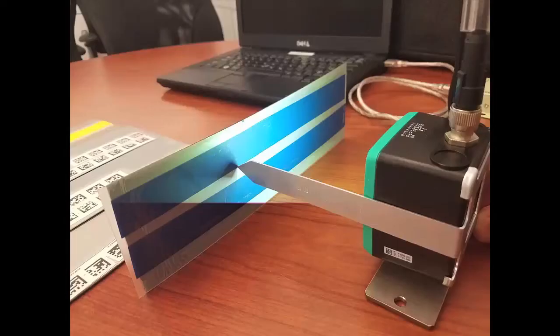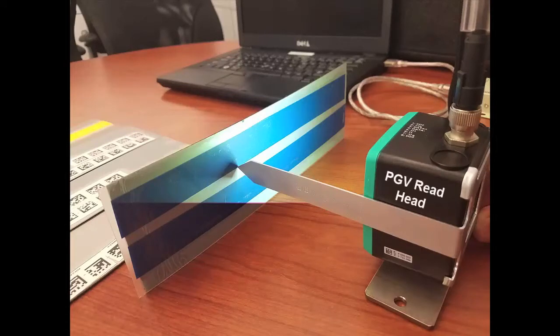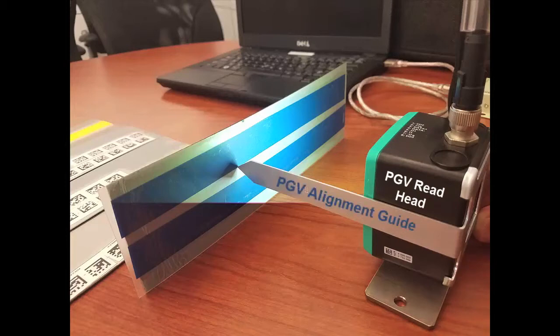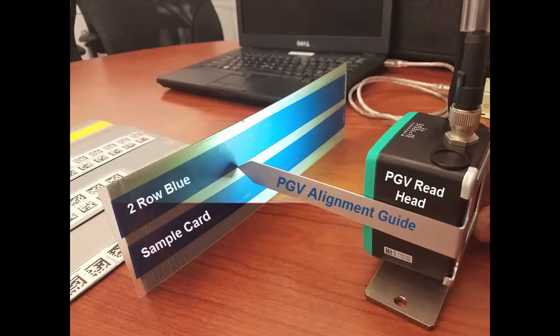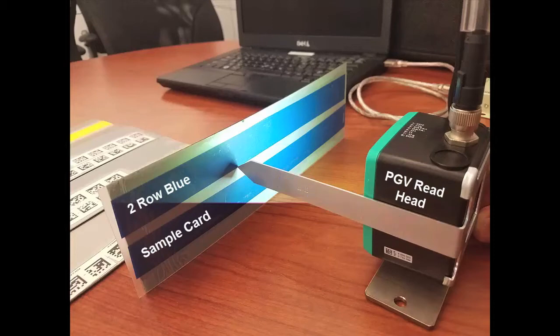Next let's introduce the actual sample card for the PGV to analyze. We can begin by aligning the PGV read head. Grab the alignment guide and hold it on the side of the read head as shown here. This guide will ensure that the read head is at the optimal reading distance from the sample card. With the read head at that distance, line the sample card up in front of the flashing camera. Once they are aligned at the proper distance, you can remove the alignment guide.